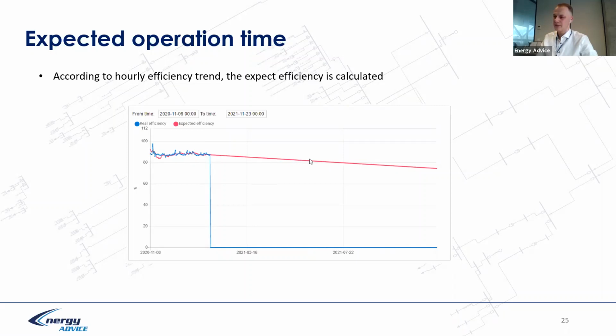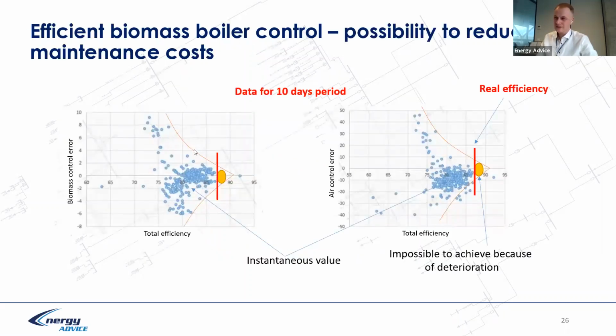That's the efficiency decrease, but on the other hand, another important thing, on this axis, is the biomass control error. The digital twin calculates the optimum set point of the biomass boiler for the control system. We can calculate the error in percentage from the real set point, and we can understand the real efficiency. And we see that efficiency is distributed: if the error increases, efficiency decreases.